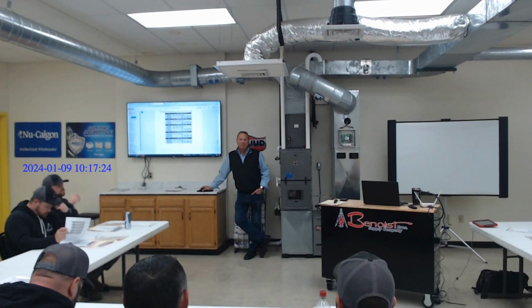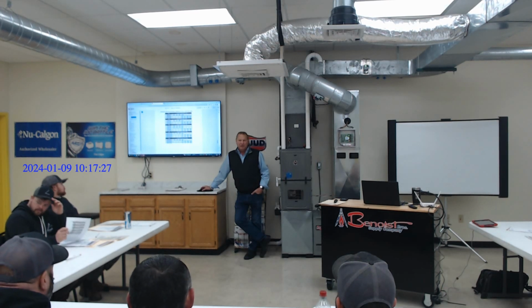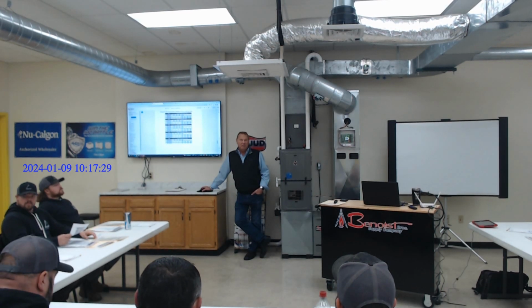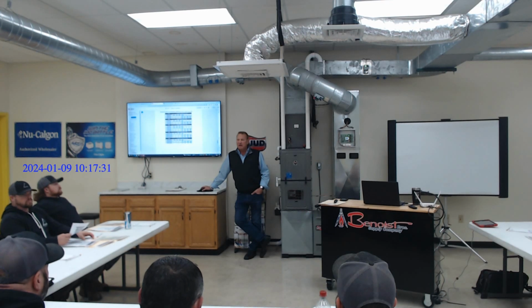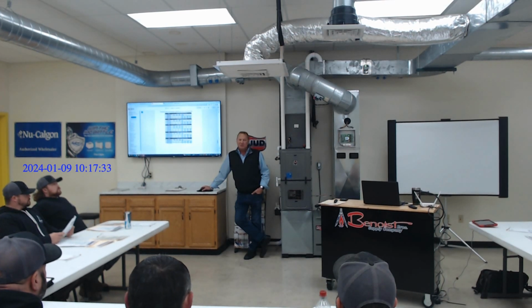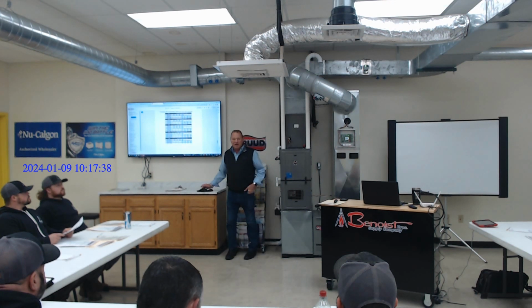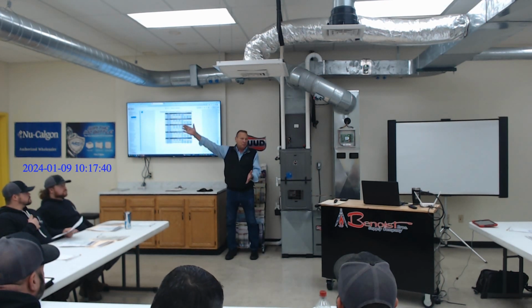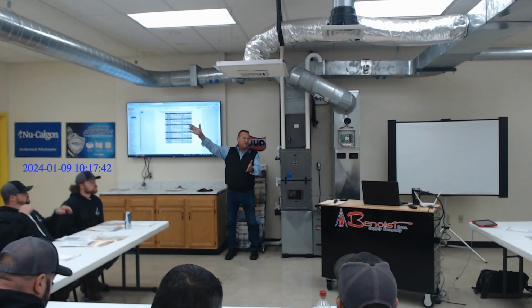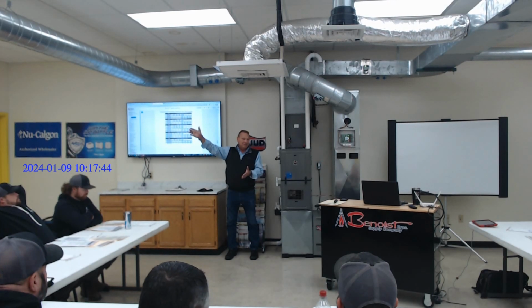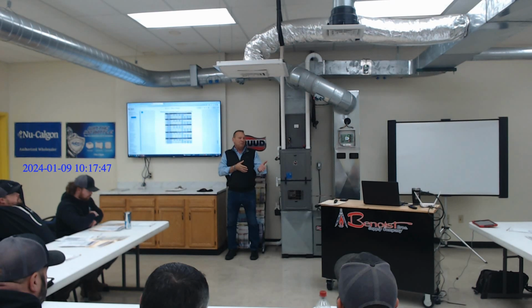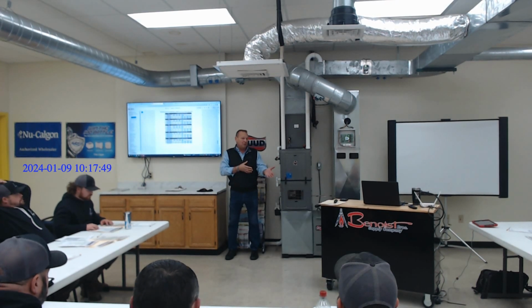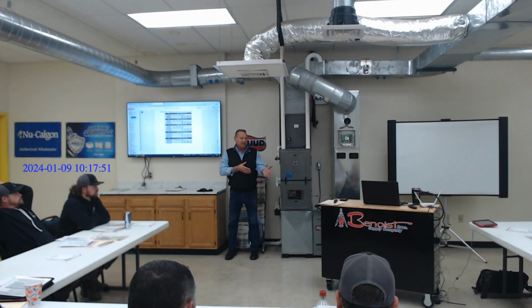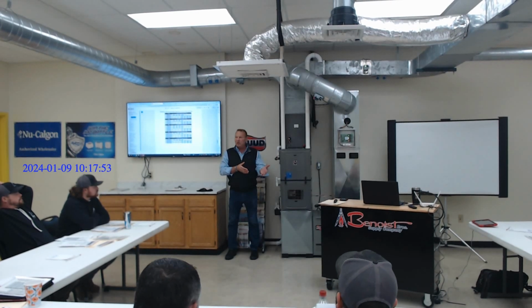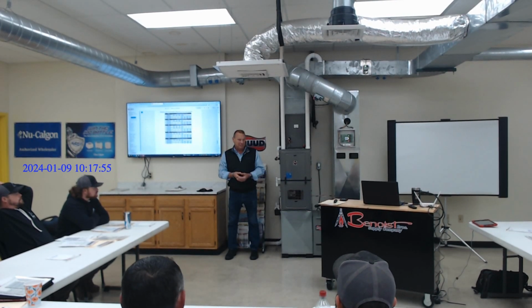I tell everybody, if you're gonna zone, and you really are limited for bypass space and all that stuff, it ain't cheap, but your best bet's your 18 SEER and your mod furnace, because I've got ranges from 45 to 100% to work with. Because when I lock in a CFM value in a zone, it's locking in how fast my outdoor unit's gonna run on the inverter speeds, and where my furnace is gonna go on its heating capacity, because my mod modulates from 45% to 100%.